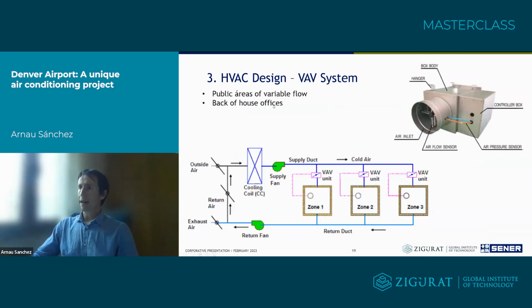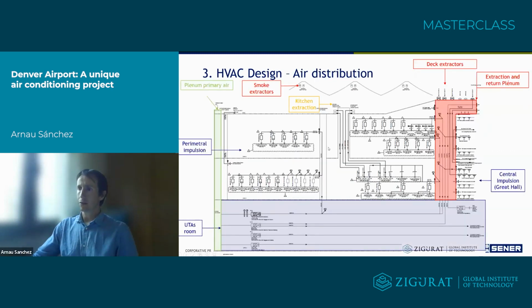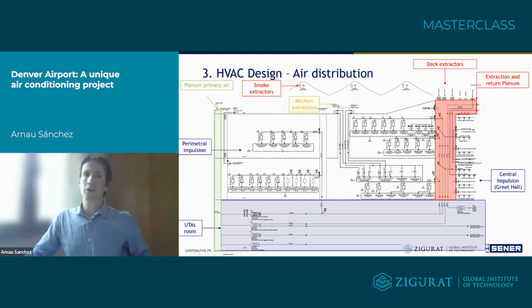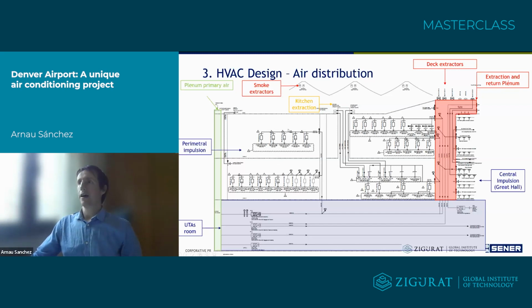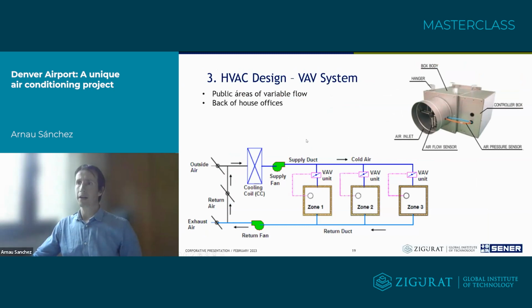Well, we have two kinds of air conditioning systems here from the air side. We have the Great Hall, which we supply through jet nozzles with a constant airflow but a variable supply temperature. And for the rest of the areas, we have a constant supply temperature and variable flow rate. For those areas, we use the VAV system, these VAV boxes. It's a very typical system in the United States. Maybe in Europe we don't use that system a lot, but it's very common there, and it provides a significant advantage: the chance to take advantage of pre-cooling many hours of the year.